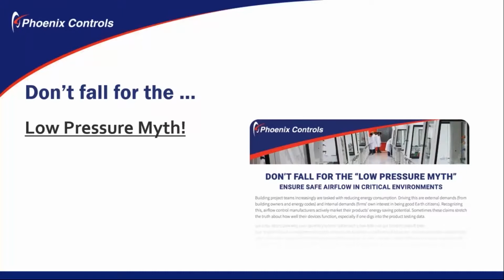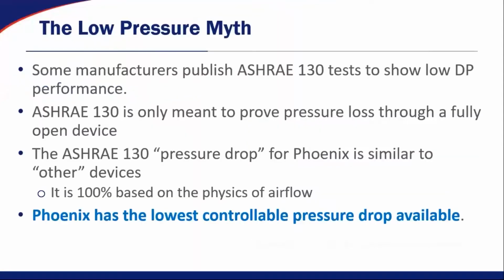Next, I want to talk about this thing we call the low pressure myth. So we have this literature piece out there called Don't Fall for the Low Pressure Myth. I highly recommend reading it if you get a chance. But what the low pressure myth is, it's actually a mindset that some people are trying to push on people, a calibrated device that comes from the factory calibrated versus something that uses an ultra low pressure drop, or what they claim is an ultra low pressure drop.